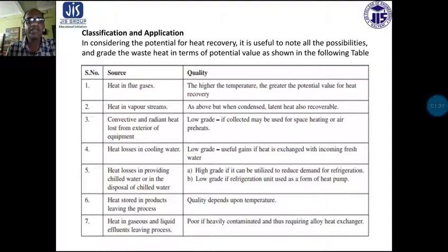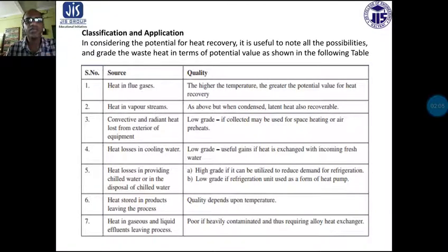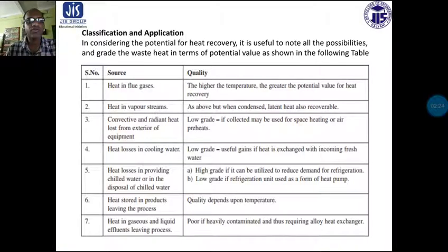Convective and radiant heat lost from exterior of equipment — quality is low grade; if collected it may be used for space heating or air preheating. Heat losses in cooling water are also low grade, and useful gains can be made if heat is exchanged with incoming fresh water. Heat losses in providing chilled water will be high grade if utilized to reduce demand for refrigeration, or low grade if the refrigeration unit is used as a heat pump.